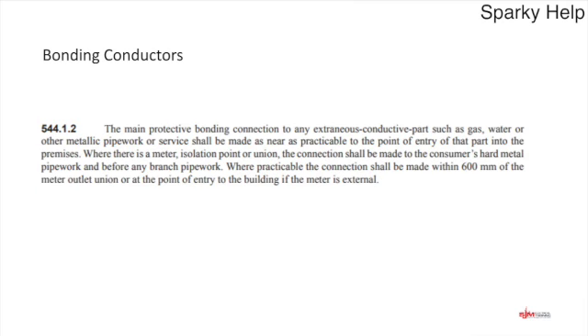So where do these go? Well, I think most people probably know, but just to make sure, they go to extraneous conductive parts. Extraneous conductive parts are parts of metalwork not part of the electrical system that go to ground and therefore earth themselves. That's the important part. They go to ground and they introduce an earth potential. Gas, water and other metallic pipework or anything else.